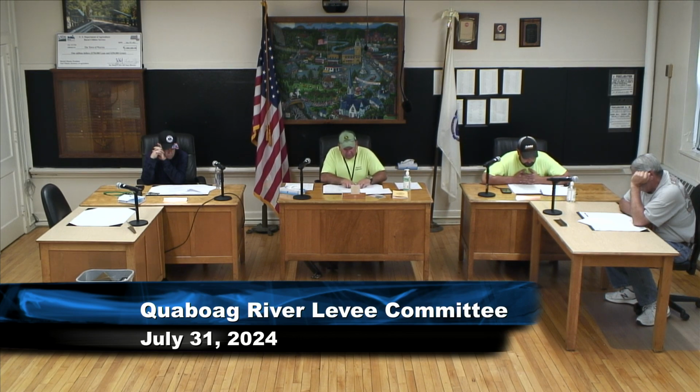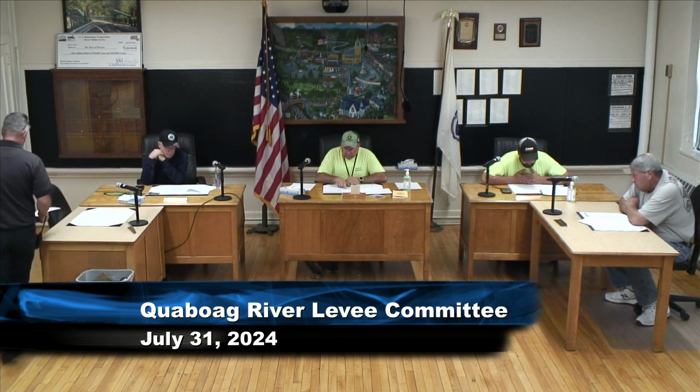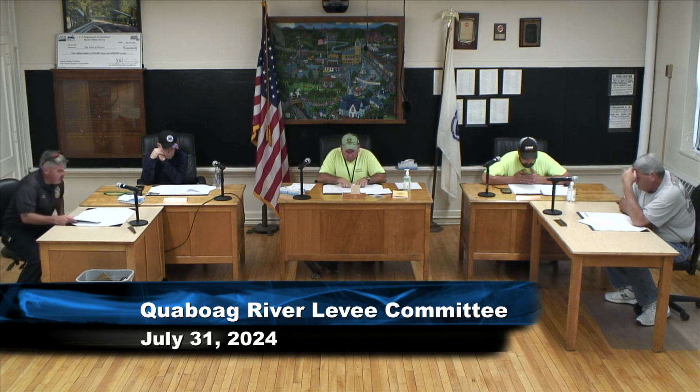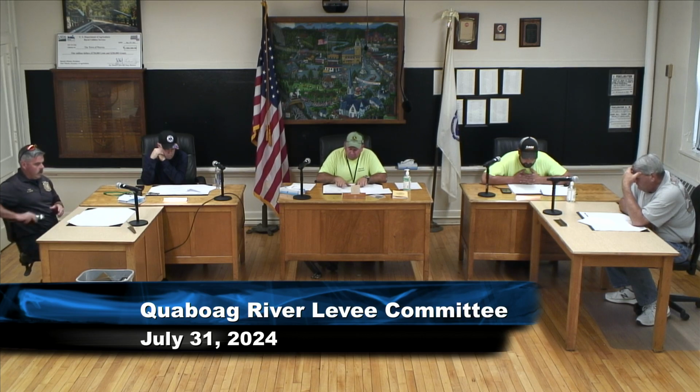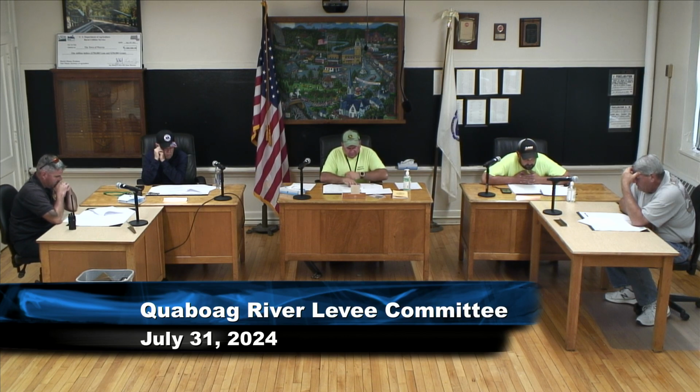June 6th, R.H. White mechanical crew was on site to assist the Warren Flood Commission in determining the condition of flood valves located at the Levee Mill building. Upon opening numerous manholes accessing the valve bodies, we found them to be in various states of disrepair. While the valves and access to the valves were available, many of the locations had collapsed walls and were full of debris. This impeded the proper inspection of the valves.